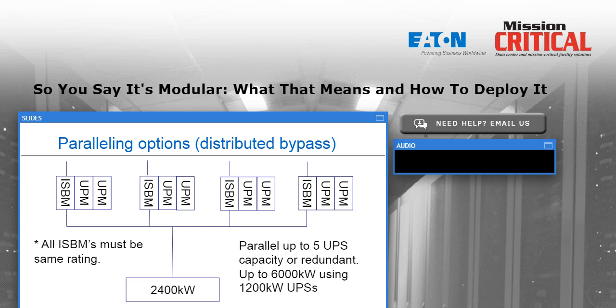Are modular UPSs more expensive than monolithic versions? Typically they are, not in every case, but a modular UPS system tends to have more parts, separate controls for each module, separate internal breakers and contactors for each module. And the general understanding is the more parts you have in a machine, the more likely a failure may occur. But keep in mind that these are usually deployed as N+1 redundant systems. So the failure of any single part will not result in a power loss to the critical load or a transfer to bypass. The system simply remains online if it is redundant until service folks get there to actually repair the UPS system. So in general, modular systems tend to be a bit more expensive and a little bit larger in terms of footprint.